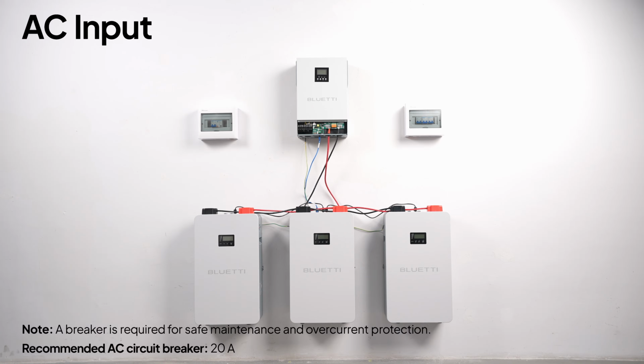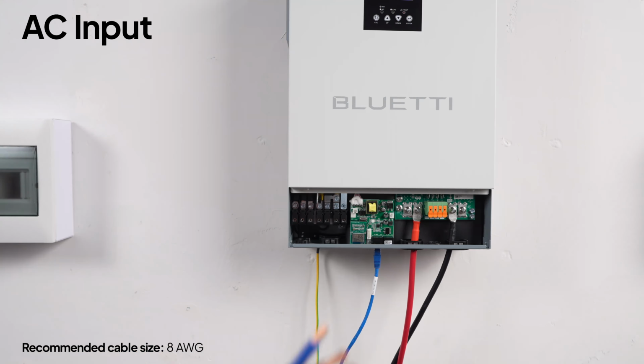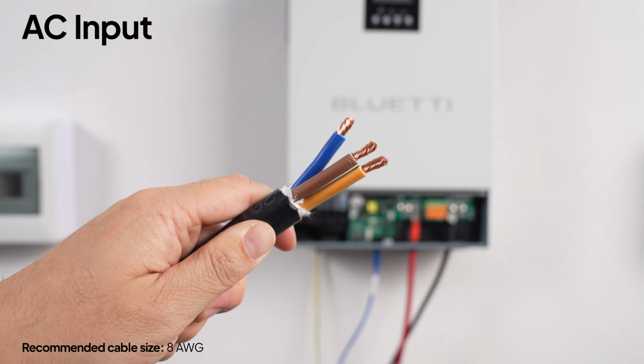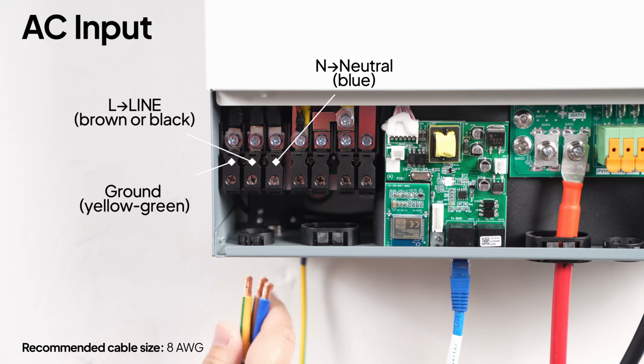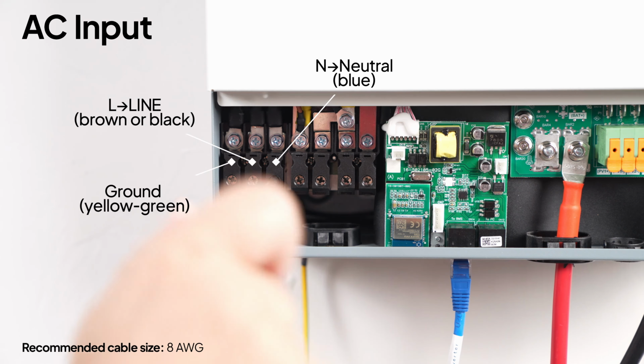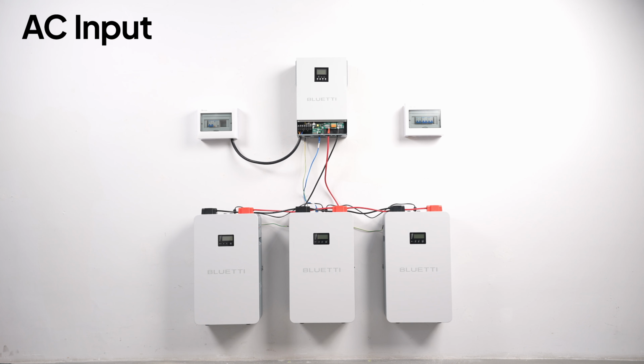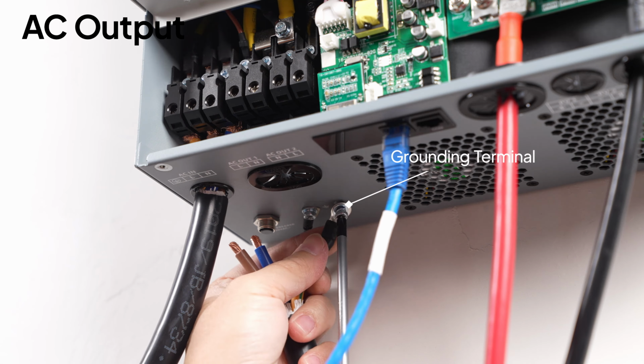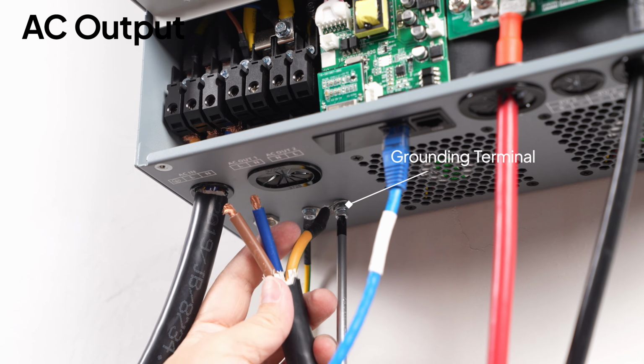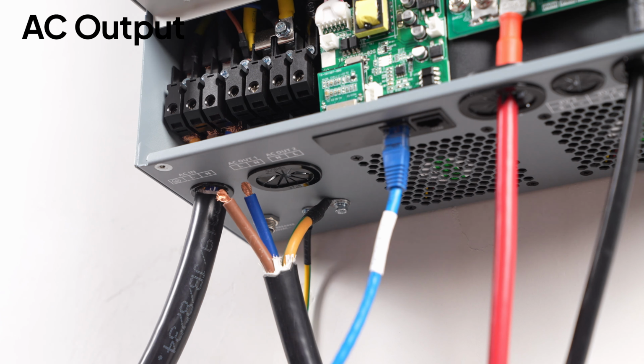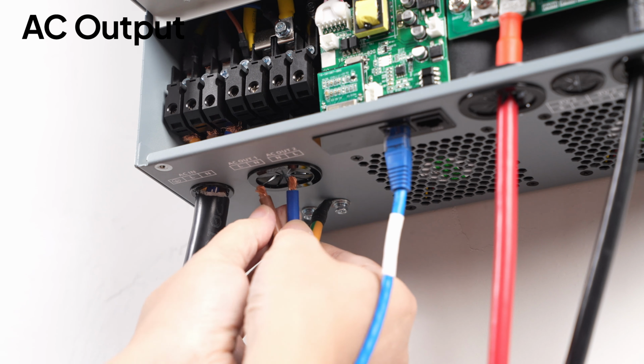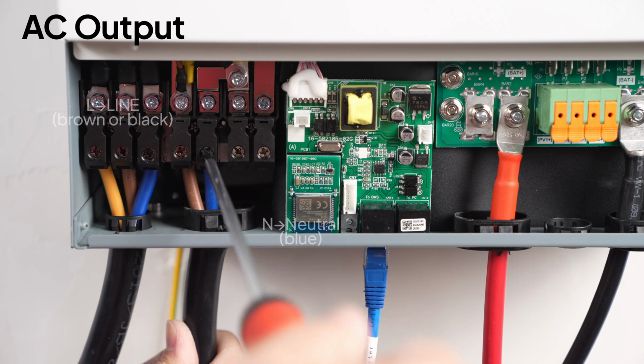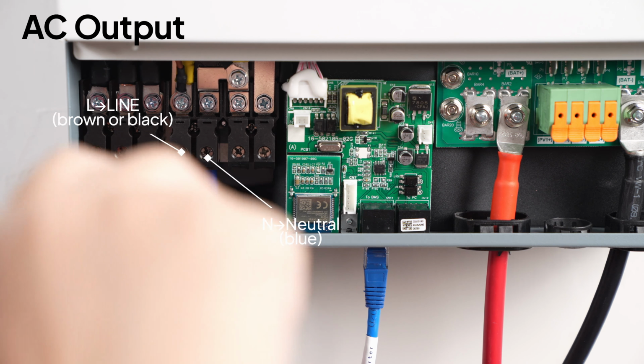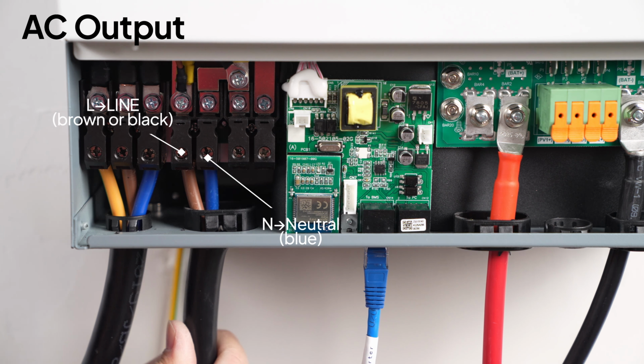Before connecting the AC input, install an AC circuit breaker between the HV10K and your main inverter panel. Strip about 10 mm of insulation from the AC input cables. Connect the grounding cable first, then live and neutral. Next, connect the AC output cables in the same order. The HV10K has 2 AC outputs, so wire both if you need to.